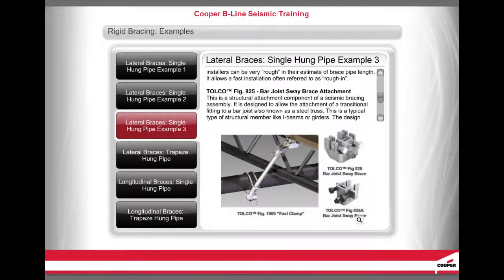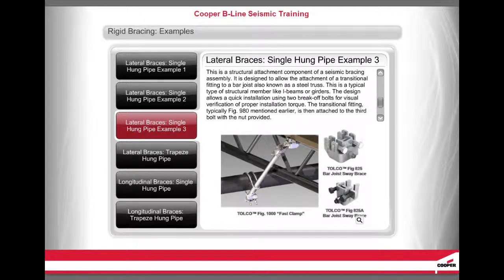The Tolco Figure 825 Bar Joist Sway Brace Attachment is a structural attachment component designed to allow the attachment of a transitional fitting to a bar joist, also known as a steel truss — a typical structural member like I-beams or girders. The design allows quick installation using two break-off bolts for visual verification of proper installation torque. The transitional fitting, typically Figure 980, is then attached to the third bolt with a nut provided.